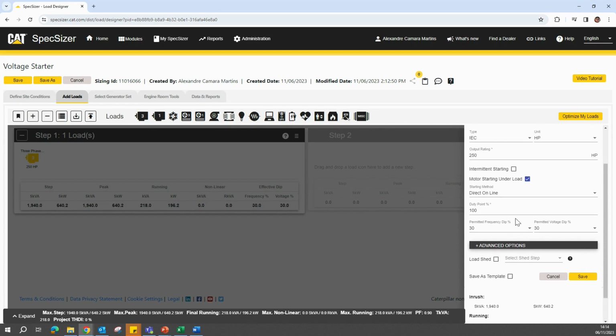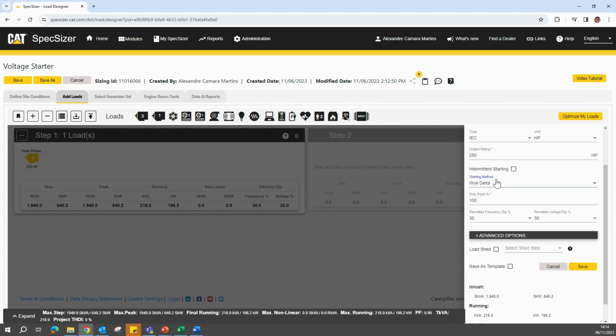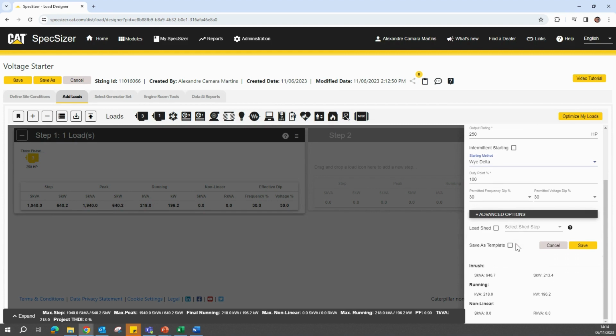On this example, we can see that the starting method selected is direct online. If we were now to consider a reduced voltage starter, for example a Y delta starter, we are going to see a significantly lower impact in regards to that inrush. The difference between them will be reduced. As we can see now, the inrush is reduced to 646.7 skVA, which is not as far from the running load as before. We can save our changes and go back to the Select Generator Set tab.